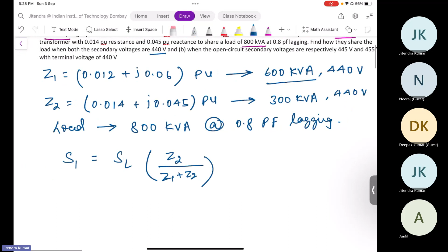The impedance value Z per unit new is equal to Z per unit old into kVA new divided by kVA old - that is a very famous formula - into kV square old by kV square new. Any doubt in this expression?